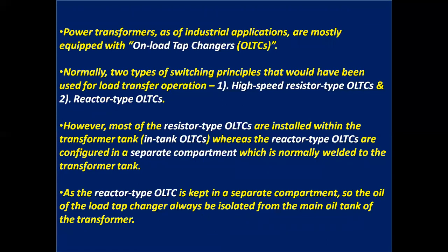Power transformers as of industrial applications are mostly equipped with on-load tap changers, that is OLTCs. Normally, 2 types of switching principles that would have been used for load transfer operation. One, high-speed resistor type OLTC, and number 2, reactor type OLTCs. However, most of the resistor type OLTCs are installed within the transformer tank, that is in tank OLTCs, whereas the reactor type OLTCs are configured in a separate equipment and separate compartment rather, which is normally welded to the transformer tank.